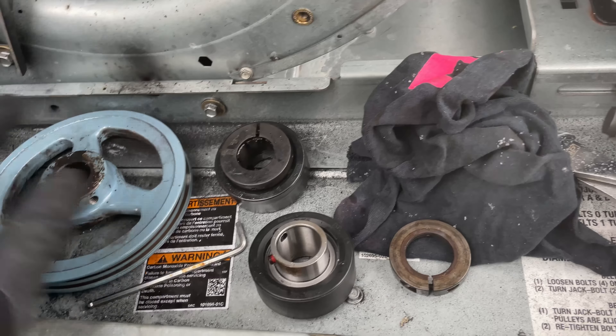It's not a good day for that kind of service — already put a panel to protect the electrical. That looks like a small rotation but the belt is vibrating because all the panels on our sides are open and the motor is running on full load — that's the reason; otherwise the belt is probably aligned. The unit is running fine now and everything is back on the panel. The weather is getting worse here. Please subscribe to my channel so I can keep uploading more troubleshooting videos. Thanks for watching.